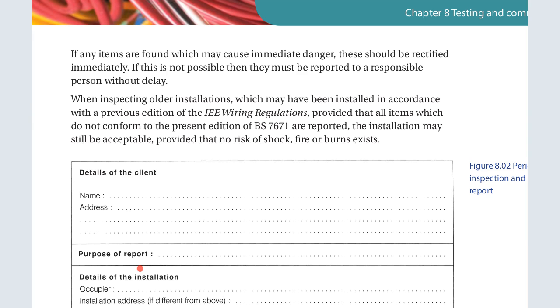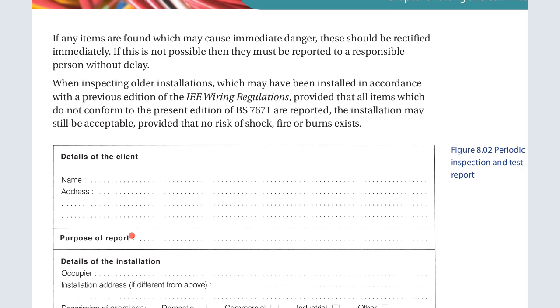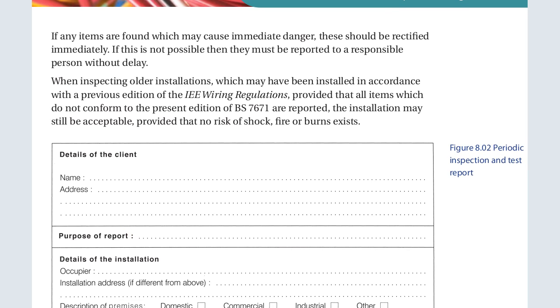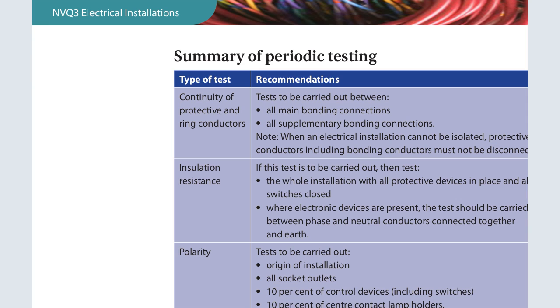If this is not possible, then you must report to the responsible person without delay. When inspecting older installations, which may have been installed in accordance with the previous edition, that is the IEE wiring regulations, provided all the items which do not conform to the present edition are reported, an installation may still be acceptable, provided that no risk of shock, fire, or burns exists.